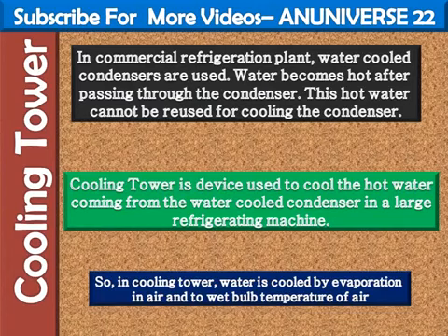The air surrounding the falling water droplets from the spray nozzle causes some of the water droplets to evaporate, and the evaporating water absorbs latent heat of evaporation from the remaining water and thus cools it. The air also absorbs a small amount of sensible heat from the remaining water.